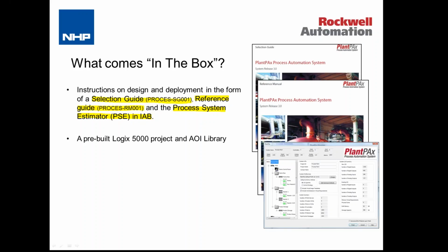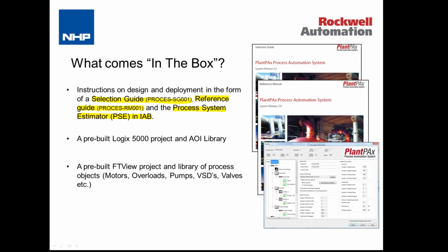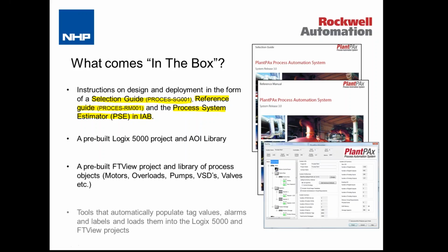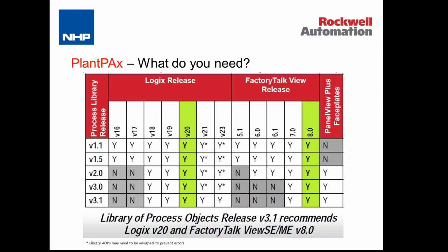So what else comes in the box? Well, we've talked about the library, and the View project. So within the library there's a template project for FactoryTalk View. So you don't need to start from scratch. There's a template project that has some screens set up, navigation system set up, has an alarm banner, has the security configured. So it really gives you a head start in getting the system up and running. And the tools. So we've got tools that allow us to automatically generate alarms, to use a spreadsheet, use Excel to do some configuration of the system, tools that really speed up the implementation of the project.